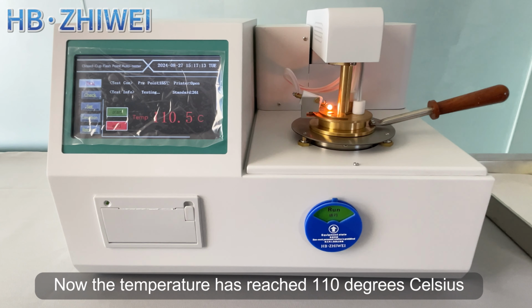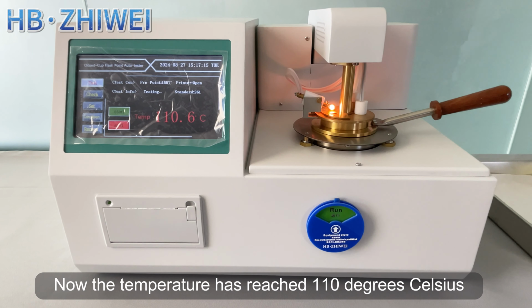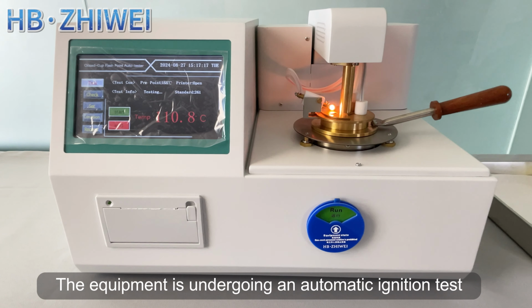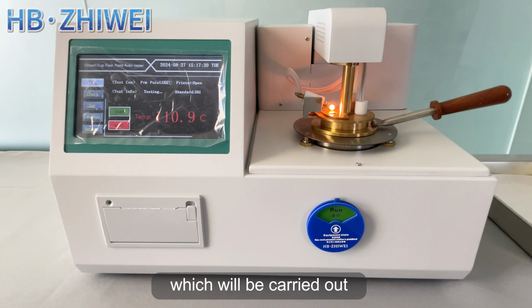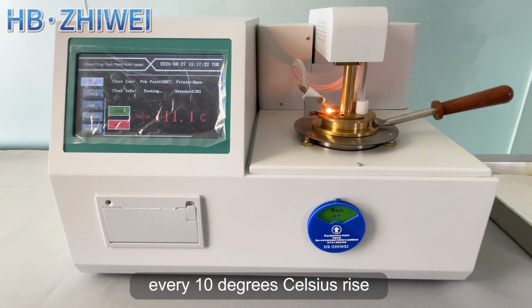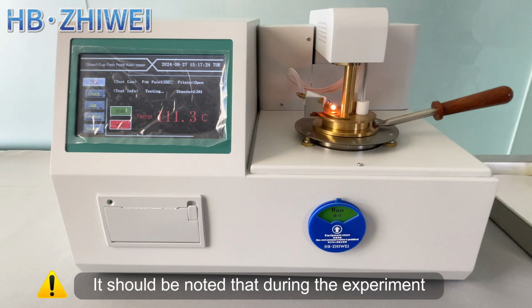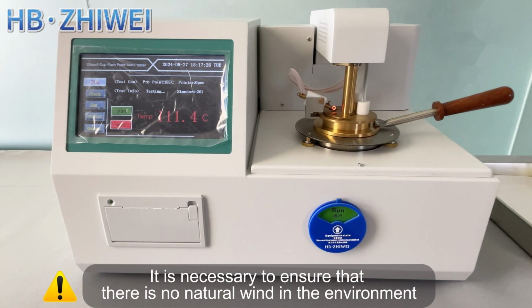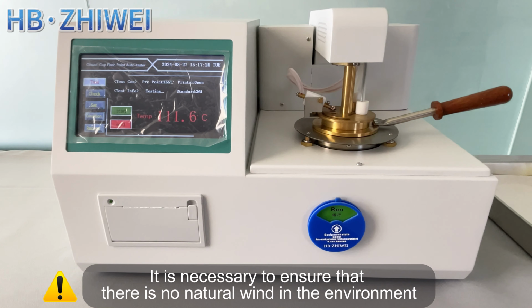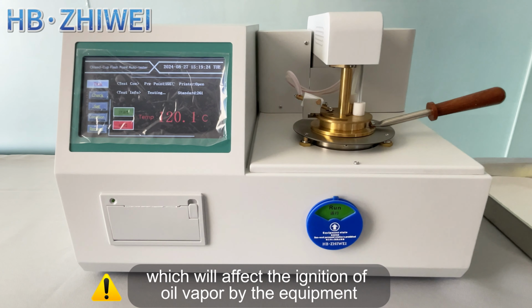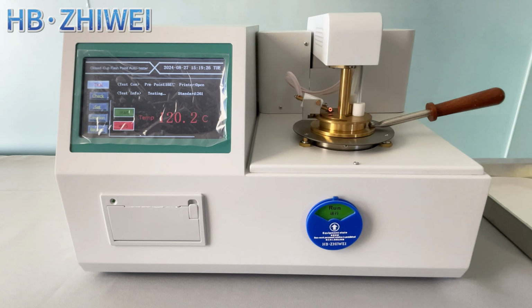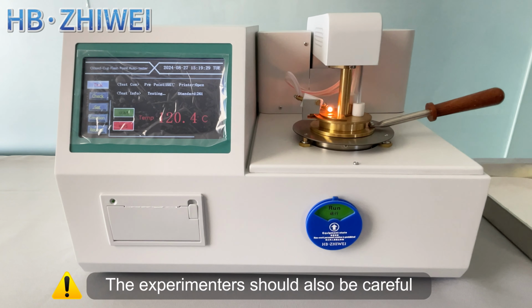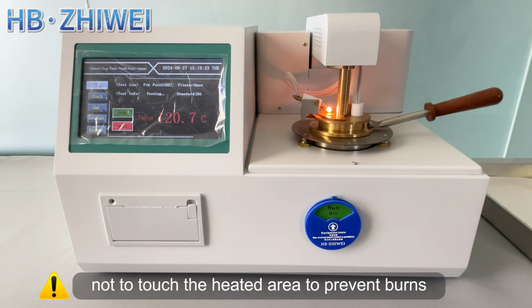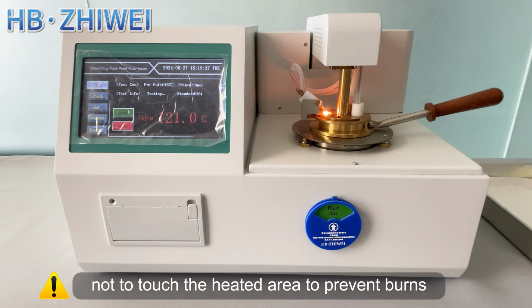Now the temperature has reached 110 degrees Celsius. The equipment is undergoing an automatic ignition test, which will be carried out every 10 degrees Celsius rise. It should be noted that during the experiment, it is necessary to ensure that there is no natural wind in the environment, which will affect the ignition of oil vapor by the equipment. At the same time, the experimenters should also be careful not to touch the heated area to prevent burns.